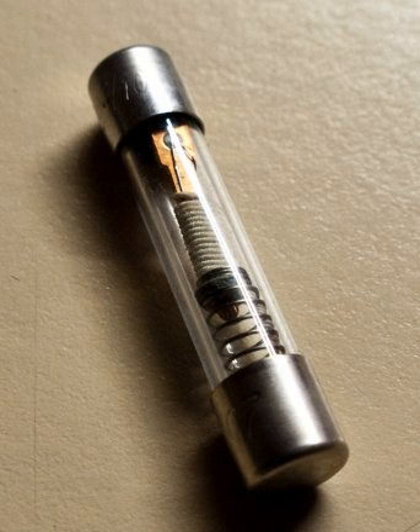HRC fuses sizes 000 and 00, here 63A and 125A rated current. HRC fuses sizes 1, 2 and 3, here 250A, 400A and 630A rated current. TAB 2007, the Technical Connection Conditions of Energy Network Operators, requires one disconnecting device per meter in the pre-metering area of customer installations. A disconnecting device is a device for disconnecting the customer system from the distribution network, which can also be operated by the customer, an electrotechnical layman.